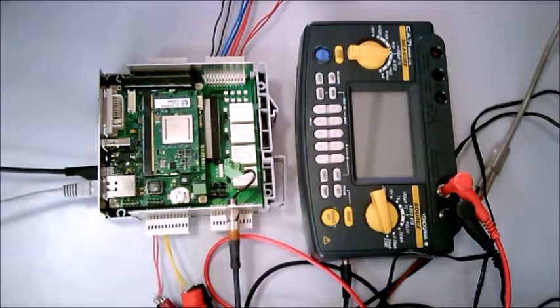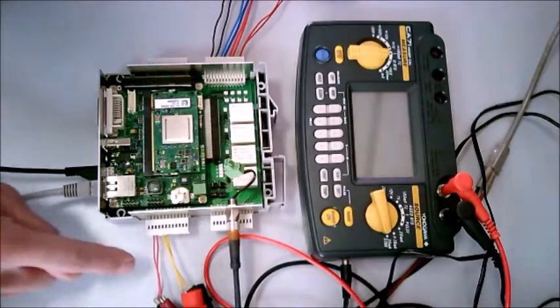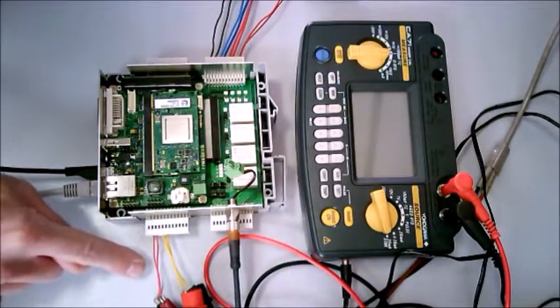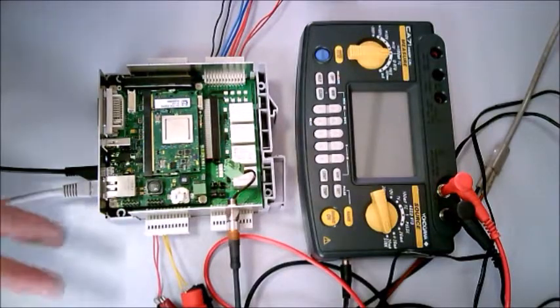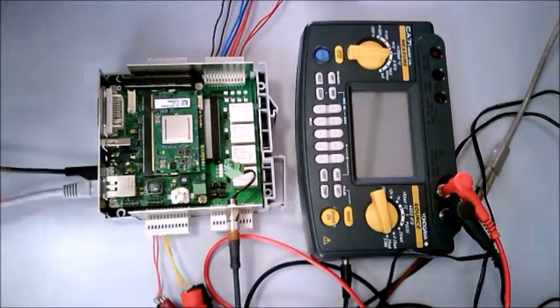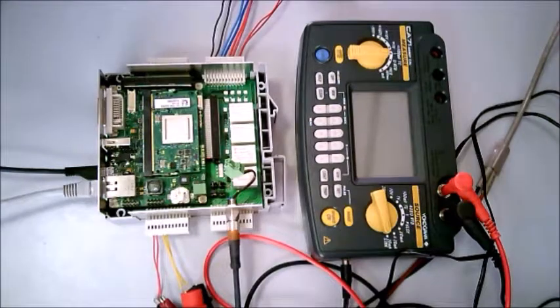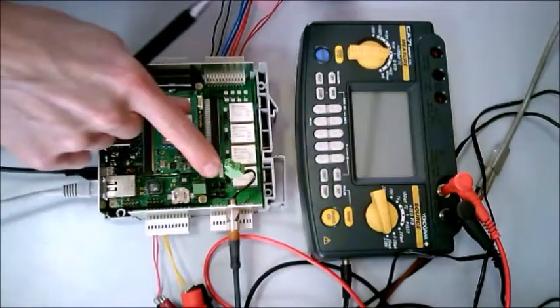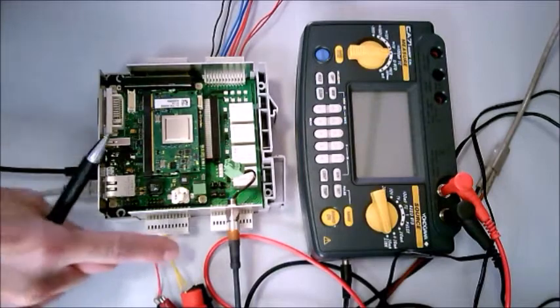And a passive connection will mean that the sensor that generates the current loop needs a supply coming from the Iris. So the Iris Box PC provides an 18 volts DC auxiliary power supply for these cases, for the passive connectors, and depending on the kind of connector we use, we should configure these jumpers. I insist that everything is explained in the user manual. So once we have configured the 4 jumpers, we have to connect according to this difference between active or passive.